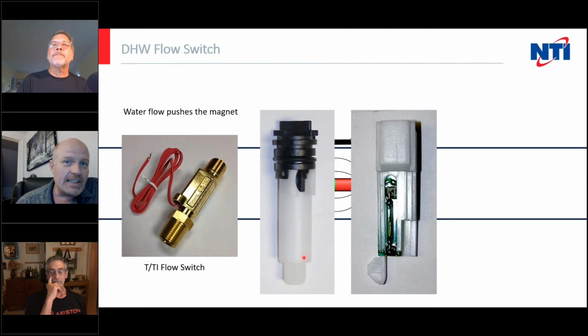So this piece here is where the magnet rides up and down inside. There's a filter at the bottom to keep large debris from getting into the flow switch. And on the dry side, on the new boilers, we actually separated it out into two pieces. The reed switch is held in this little glass tube here, and there's two little metal contacts. So one way you can test these is if you have a magnet in your toolbox, hold it next to the reed switch. These reed switches can be just pulled out of the boiler. You just tug on the wires, the whole switch comes out.